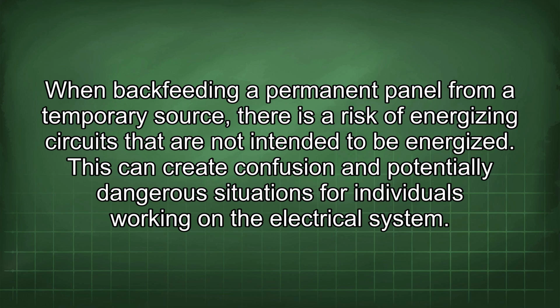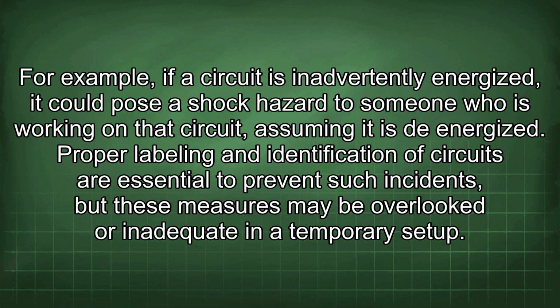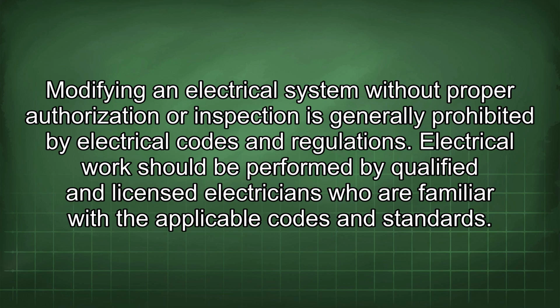When backfeeding a permanent panel from a temporary source, there is a risk of energizing circuits that are not intended to be energized. This can create confusion and potentially dangerous situations for individuals working on the electrical system. For example, if a circuit is inadvertently energized, it could pose a shock hazard to someone who is working on that circuit, assuming it is de-energized. Proper labeling and identification of circuits are essential to prevent such incidents, but these measures may be overlooked or inadequate in a temporary setup. Modifying an electrical system without proper authorization or inspection is generally prohibited by electrical codes and regulations.